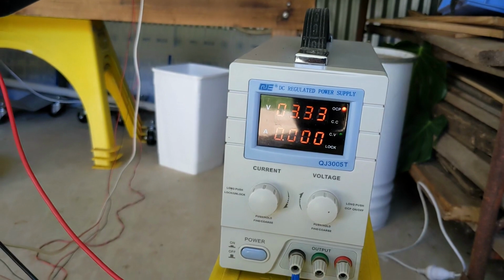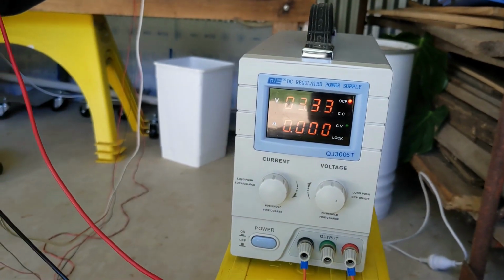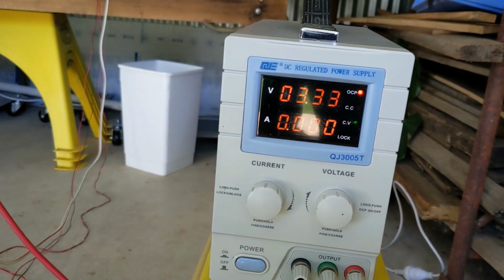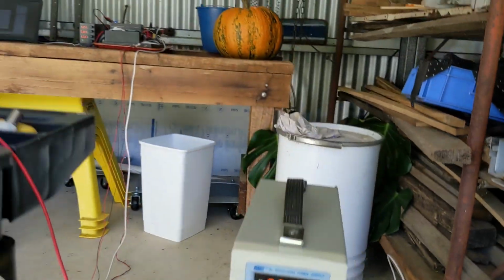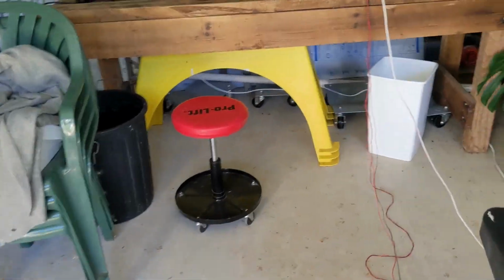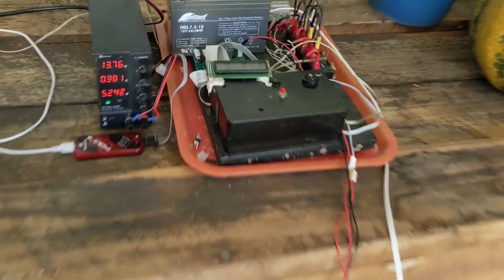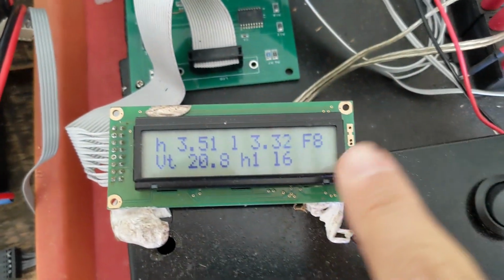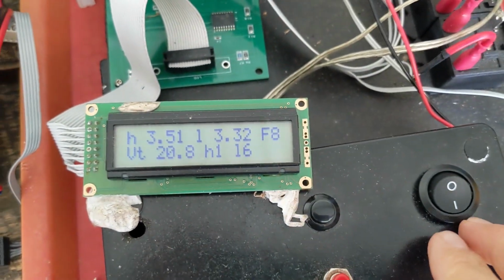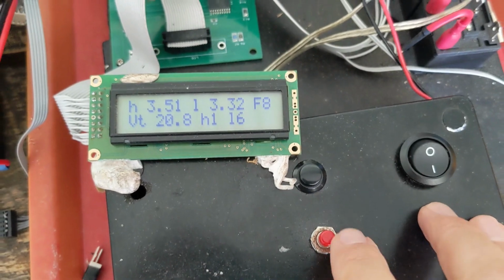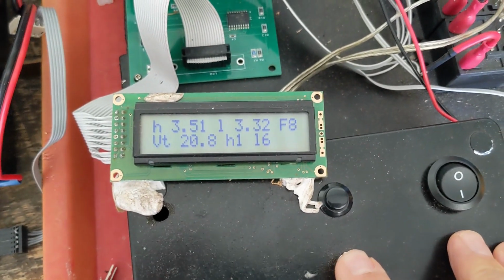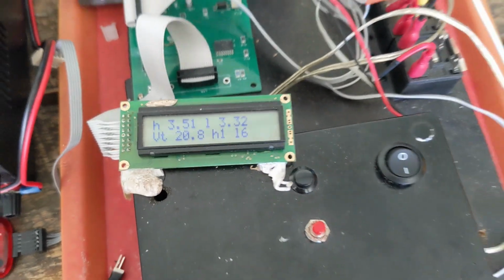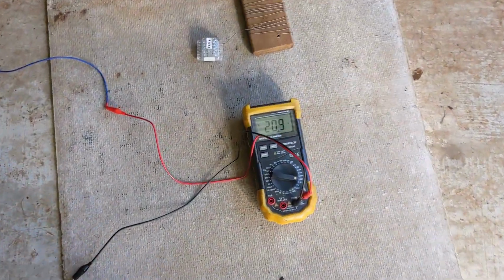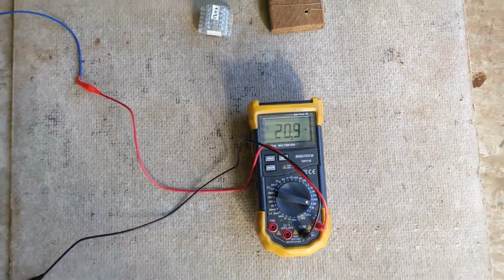Now it's gone out and it won't come back again with the voltage turned up. I need to go and reset it. So you can see F8 there, that means fault 8, it means one of the cells has gone low. And if I reset it by doing this, then it's back to 20 volts on our load here.